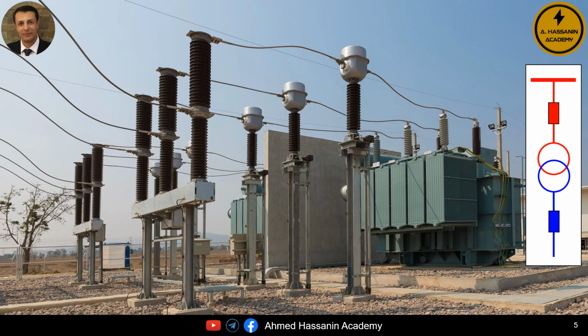Let us assume, for example, that it is required to disconnect this transformer for maintenance work or for testing or for any other work that will be carried out on this transformer. Of course, we all know that the disconnection process starts by disconnecting the loads first, followed by disconnecting the transformer from the secondary side, and finally disconnecting the transformer from the primary side. Now let us assume that the maintenance work, testing, or any other required activities on this transformer have been completed, and it is now required to re-energize the transformer, reconnect it, and return it to service once again. Of course, we must understand that the steps for energizing a power transformer are the reverse of the steps for disconnecting a power transformer. This means that in order to energize the transformer, apply voltage to it, or return it to service, we must begin by connecting the primary side first.